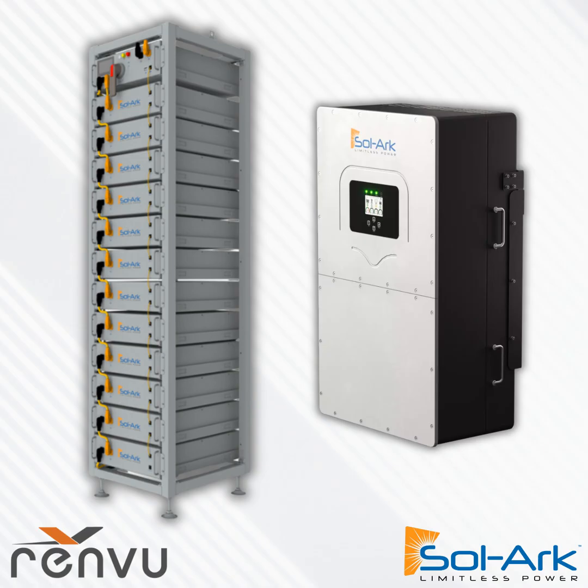It can be as simple as putting a Sol-Ark 15K on each apartment complex unit, plugging batteries and solar directly into each unit, with each unit individually owned and operated. What you have to look out for is apartment complexes that are actually on three-phase service, two legs of three-phase service, not 240-volt service.